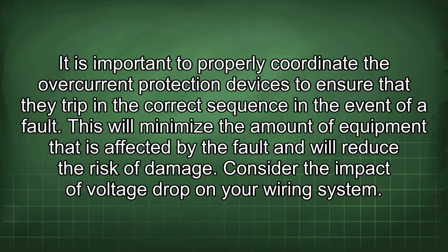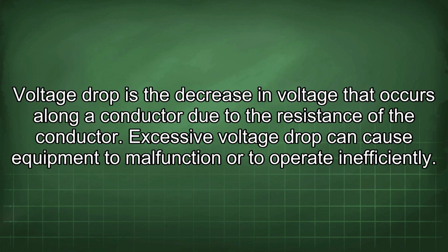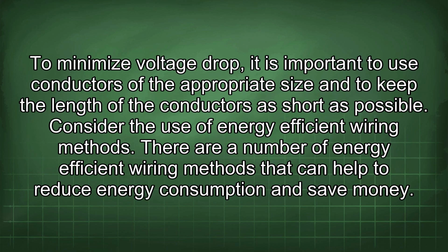Consider the impact of voltage drop on your wiring system. Voltage drop is the decrease in voltage that occurs along the conductor due to the resistance of the conductor. Excessive voltage drop can cause equipment to malfunction or to operate inefficiently. To minimize voltage drop, it is important to use conductors of the appropriate size and to keep the length of the conductors as short as possible.